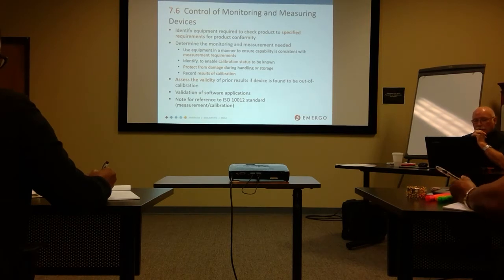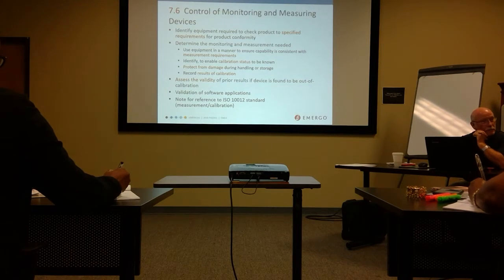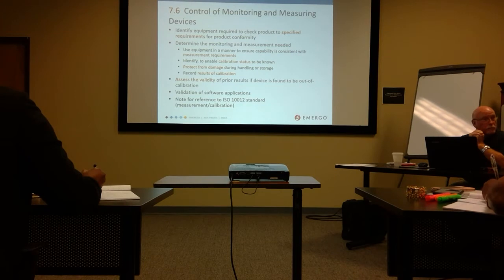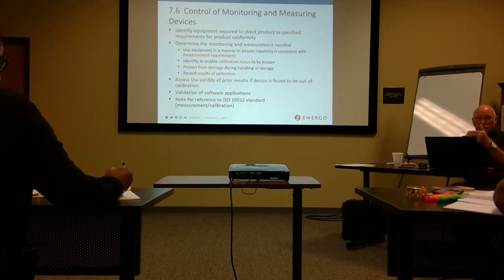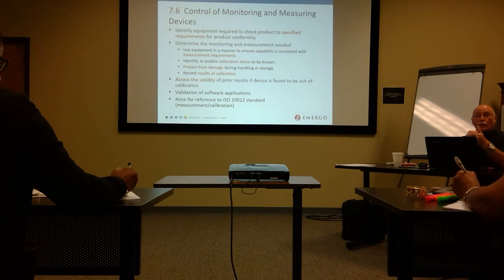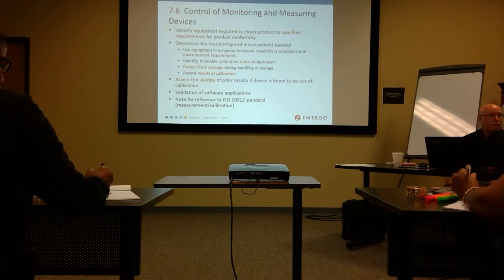One issue that we found in the last audit was the label was illegible. Illegible, yeah. We learned that it has to be legible. Yeah, good point. The whole point of the label is so that the user of the equipment is supposed to check it to make sure it's within calibration. Well, if he or she cannot read it, it's somewhat pointless. Yeah, I'll cite you for that in a heartbeat.